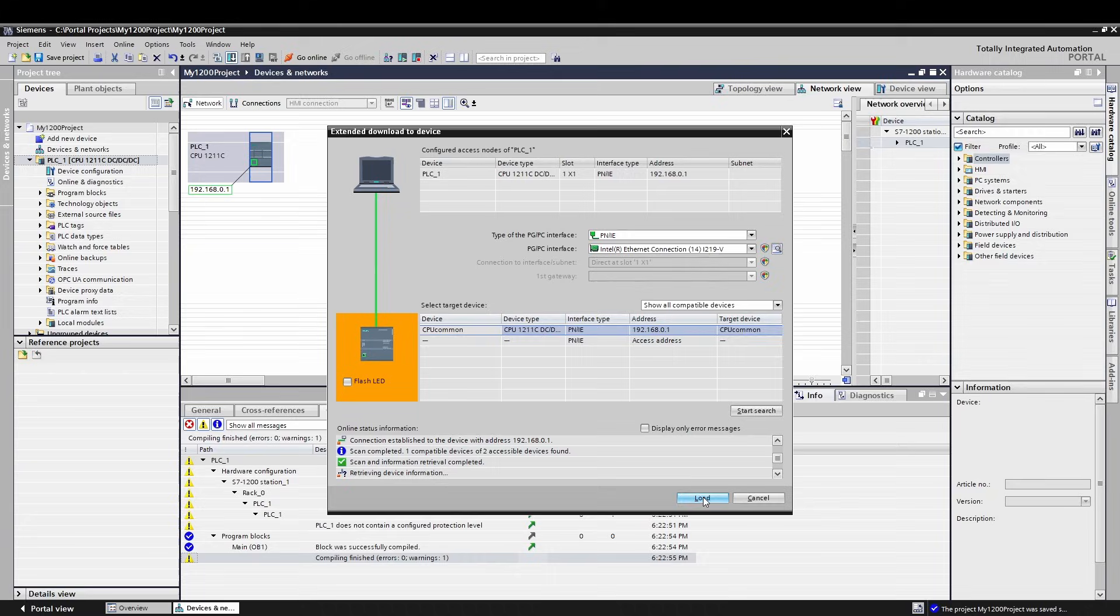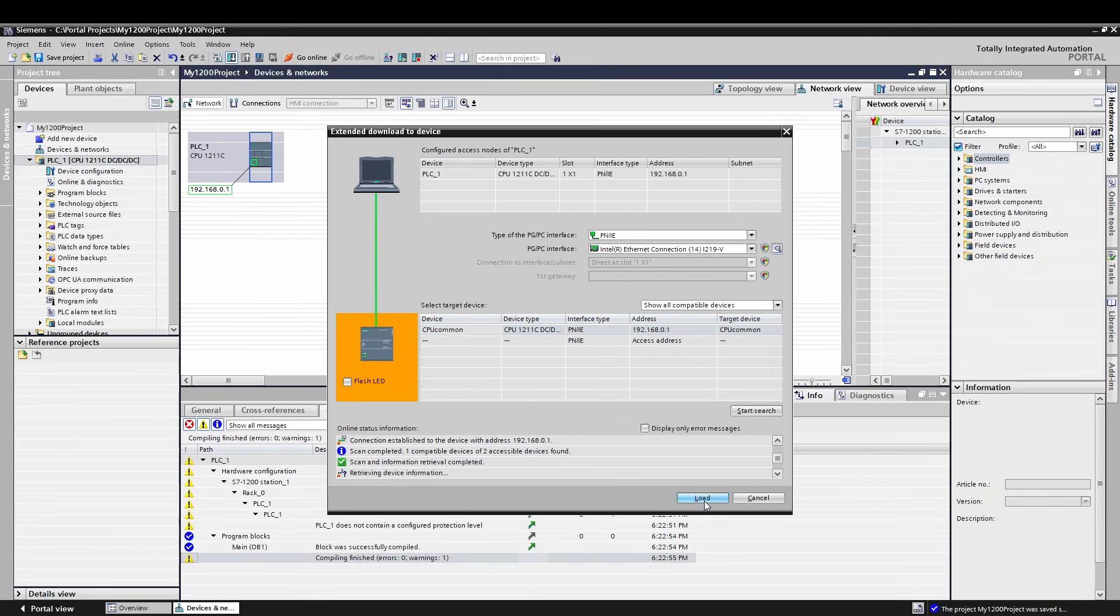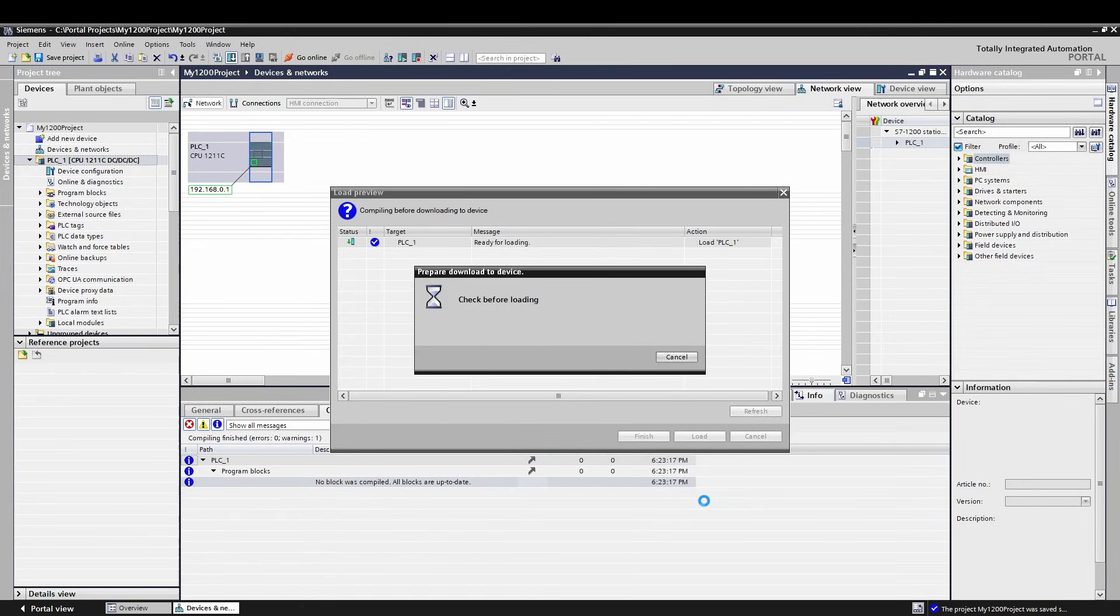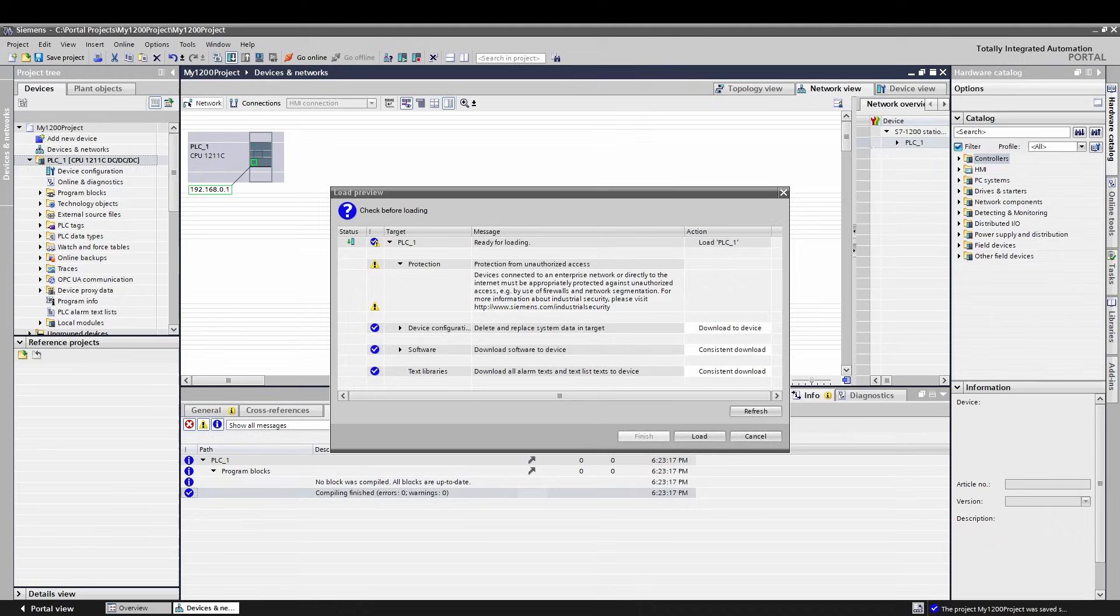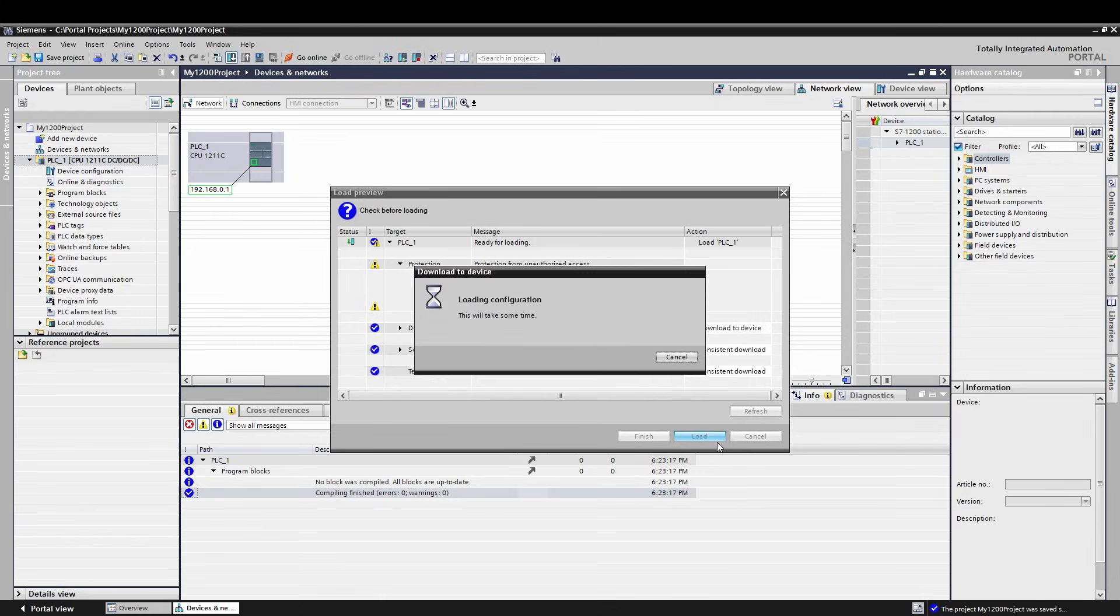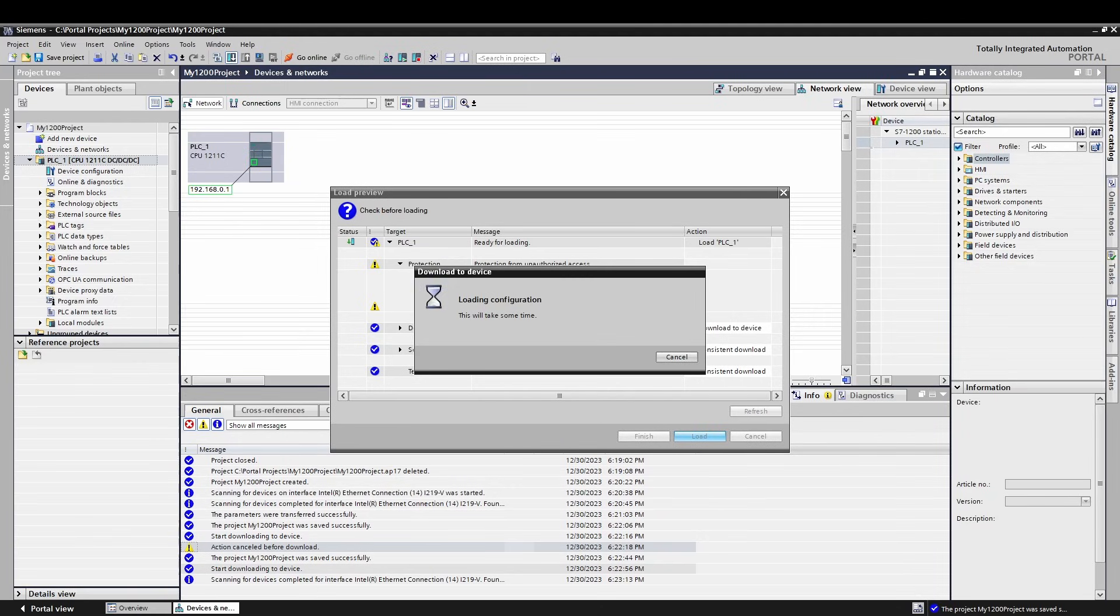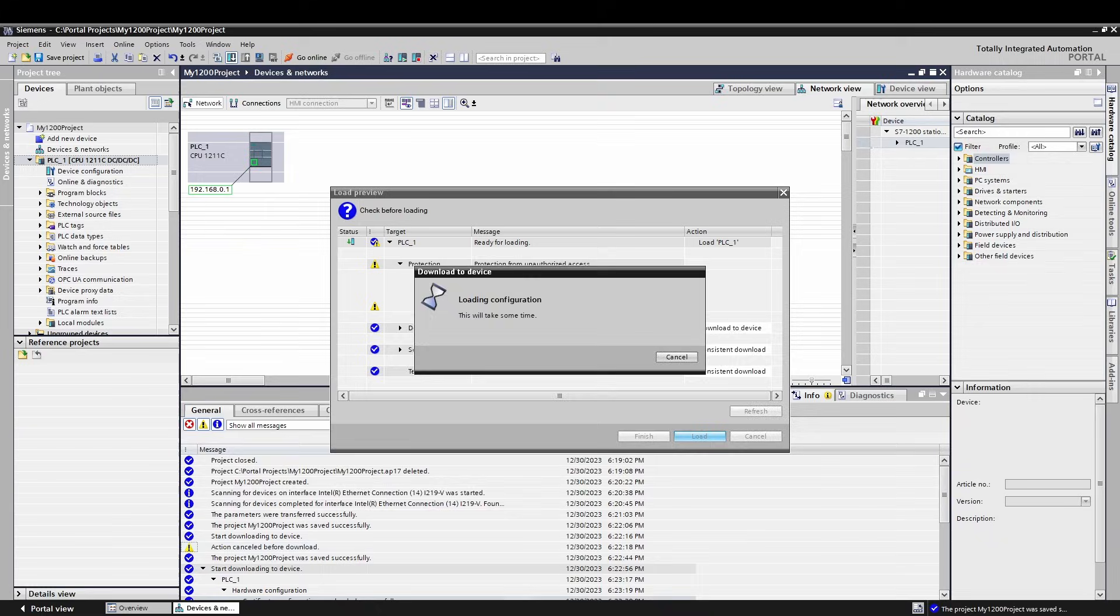This will attempt to download to whatever you have selected, so make sure to have the PLC and not some other device selected. We can now select our network card. Select PROFINET IE and select Devices with Same Addresses. This should find the device as quickly as possible. If you did not set up the device previously, select All Compatible Devices to do a search for any S7-1200s that Portal can see on the selected interface. This might turn up multiple devices, so make sure to be downloaded to the correct one if there are. Click Download and it should compile the hardware and download to the processor.